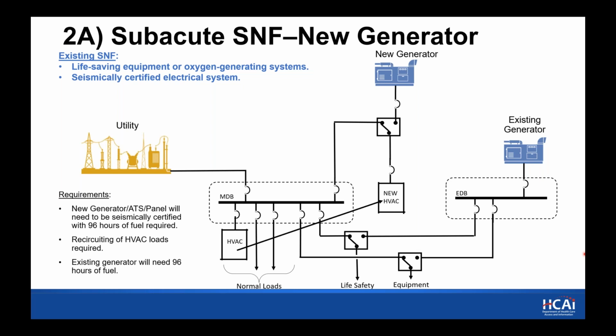And obviously with the new generator, there's another option. The other option is that you would put in a new electrical system and feed it to the new, what we say on this drawing, the new HVAC panel that's being fed from the new generator. You could then transfer those loads or add new loads to that new panel to meet the life-saving equipment and oxygen generator system backup requirements. And in that case, your new generator would cover the 96-hour fuel requirement, and your existing generator could remain as is, which is probably 6 hours. It's challenging to hypothetically look at all these before they've come in, but what we tried to do was look at some of the options or things that we might see and provide guidance.